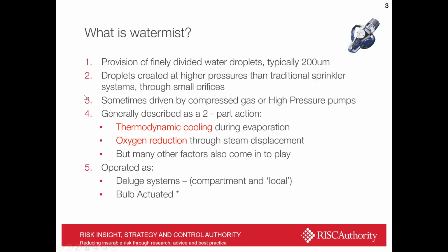So I'm not going to go into the details of this, but what is Watermist? Essentially, it differs from things like sprinkler systems because the water droplets are very finely divided to be much smaller. And in doing so, that gives them an amazing surface area for the exchange of heat and mass. So if you want to change a lot of water into steam very quickly, the first thing you do is to cut it up as fine as possible and make it available for boiling off. And this is the difference between really a Watermist system and a sprinkler system.